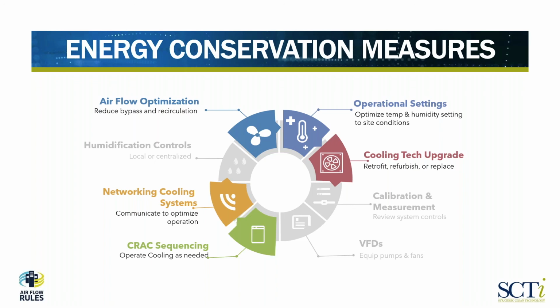Then we look at operational settings. What's the temperature, what's the humidity set points on your CRAC units, and how much can we push those up? Because the higher we can push those from a temperature point of view, the more efficient your cooling unit is going to run, and equally so, the less energy it's going to consume.